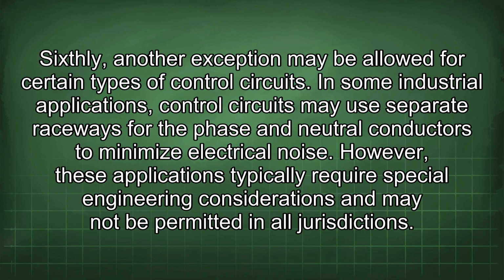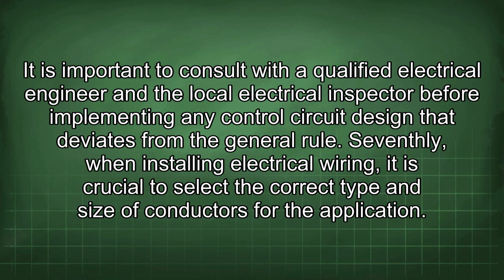Sixthly, another exception may be allowed for certain types of control circuits. In some industrial applications, control circuits may use separate raceways for the phase and neutral conductors to minimize electrical noise. However, these applications typically require special engineering considerations and may not be permitted in all jurisdictions. It is important to consult with a qualified electrical engineer and the local electrical inspector before implementing any control circuit design that deviates from the general rule.